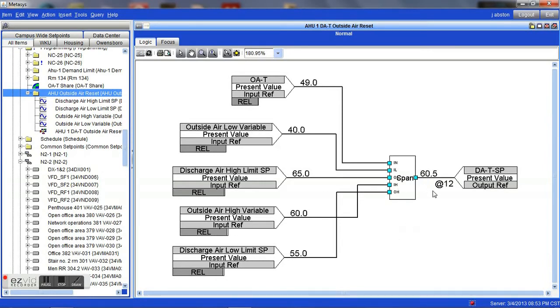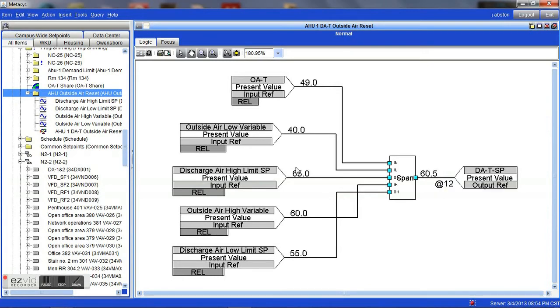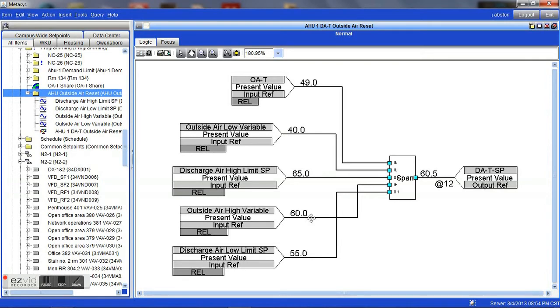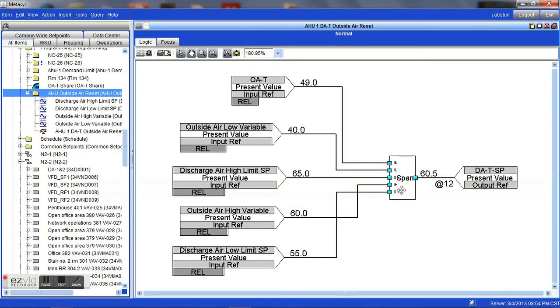Now, as you can see here for our air handler, we currently have a set point of 60.5 degrees based upon an outside air temperature of 49 degrees as well as the low variable and high variable set points combined with our minimum and maximum discharge temperature set points. If one of these are changed, it can easily change the discharge temperature set point.